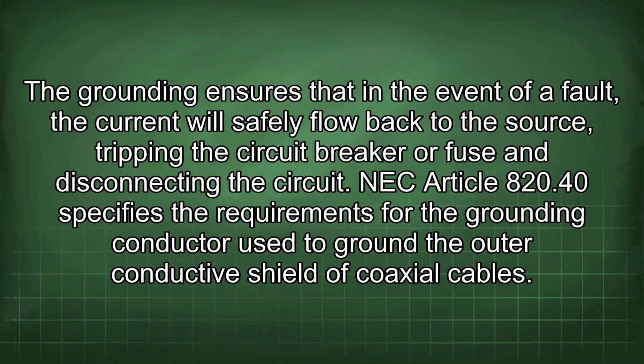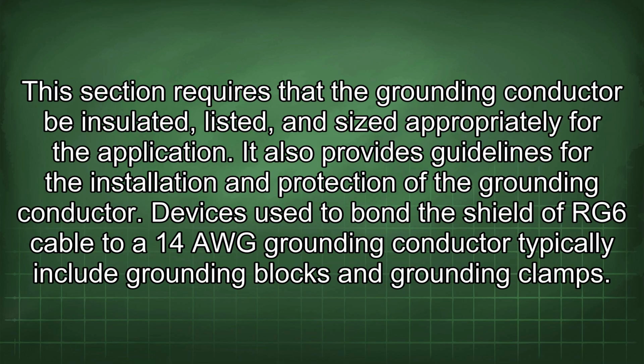NEC Article 820.40 specifies the requirements for the grounding conductor used to ground the outer conductive shield of coaxial cables. This section requires that the grounding conductor be insulated, listed, and sized appropriately for the application. It also provides guidelines for the installation and protection of the grounding conductor.